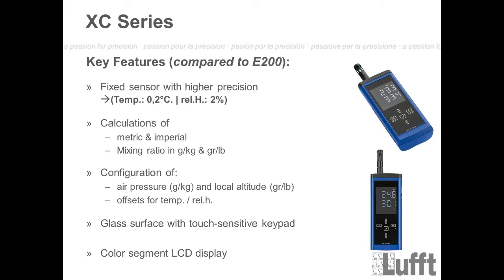In addition, you will be able to do a 1-point calibration with this device, meaning you can enter an offset for temperature and humidity. To be clear, the XC200 will only measure temperature and humidity with a fixed measurement probe.